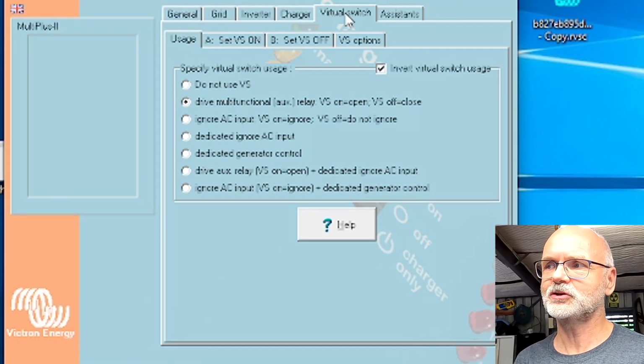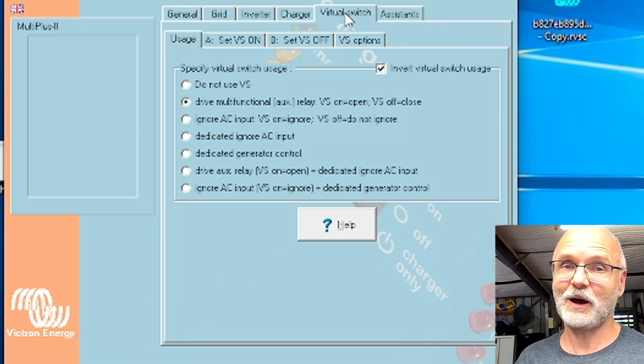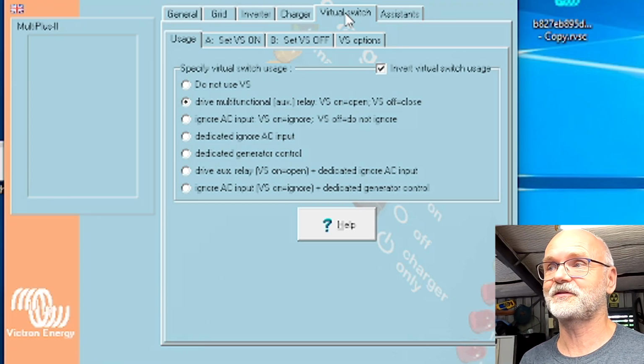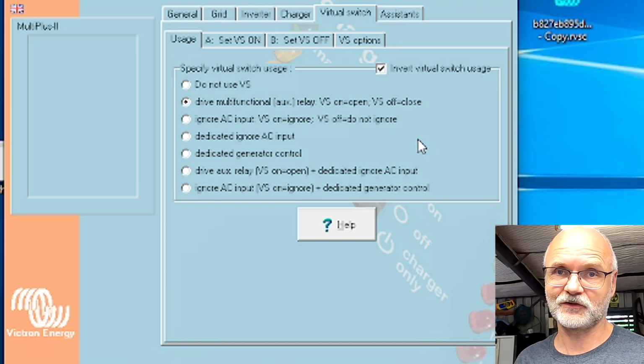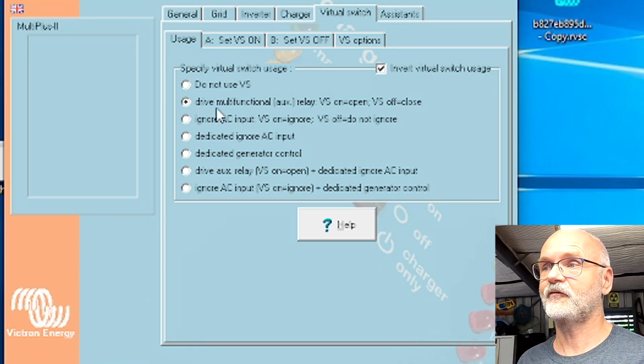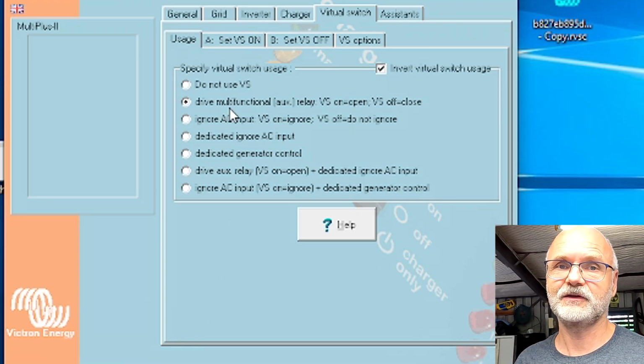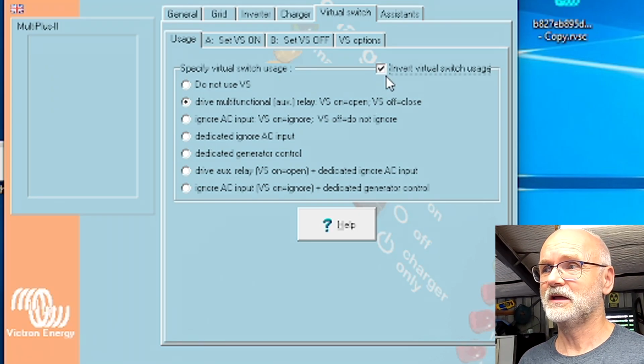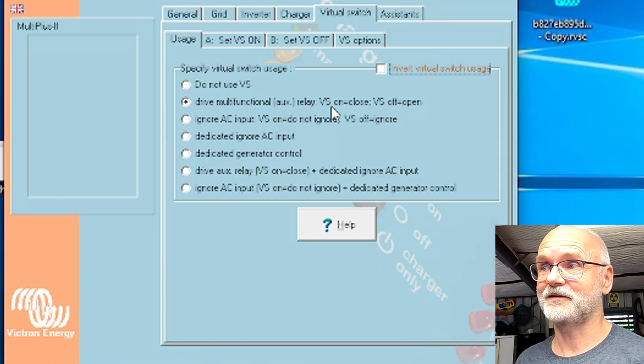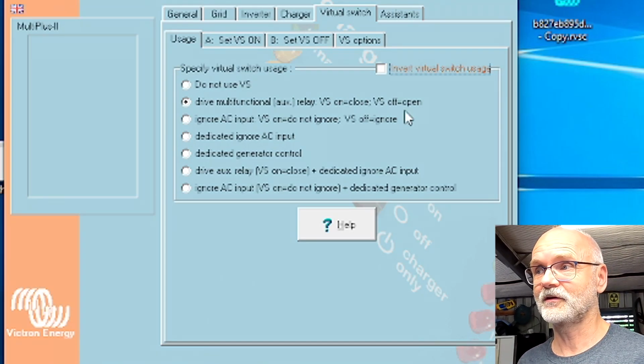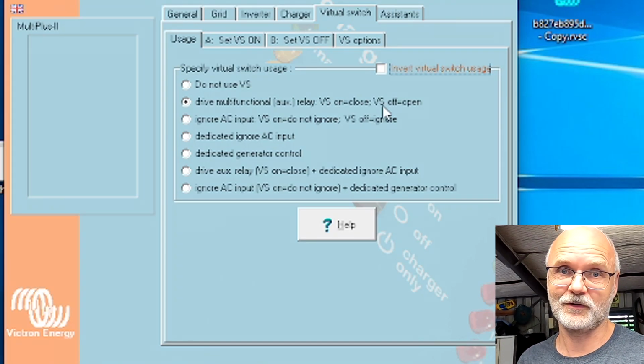Okay, here in the Virtual Switch tab, we now have a very important and very powerful feature of the Multiplus. We can now link this virtual switch to our internal relay. And this is the default setting for the Multiplus, drive the multifunction relay. And for some reason, the switch configuration is inverted by default. So I would always recommend untick this one. And then you have the right mindset, you know, on means close, off means open for the relay.